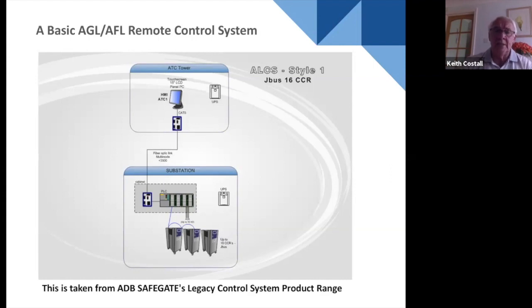But the principle is exactly the same. To communicate from the air traffic controller down to the substation, we no longer have kilometers and kilometers of hard wire—we likely have a fiber optic network, so we need fiber optic converters. We have the human machine interface, the HMI, up in the tower, talking via a fiber optic converter through a dedicated or shared fiber optic network, down to the substation where the PLC is. The PLC can then communicate to the CCRs either by a digital data communication system or by hardwire. So there are those two options.